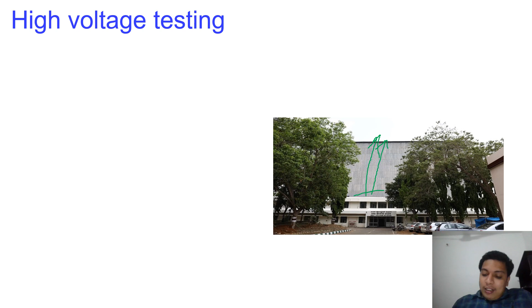Testing is done to ensure whether a device, manufactured or under operation, is reliable or not. For example, you have an overhead insulator and the manufacturer says it will withstand 100 kV. Before installing it, you should test whether it can withstand 100 kV. Since the nominal voltage is 100 kV, the insulation won't always face just that; it will face over voltage, switching over voltage, and even lightning over voltage.